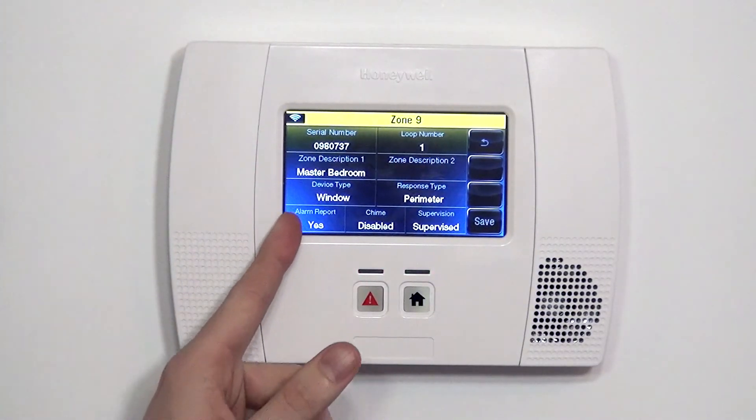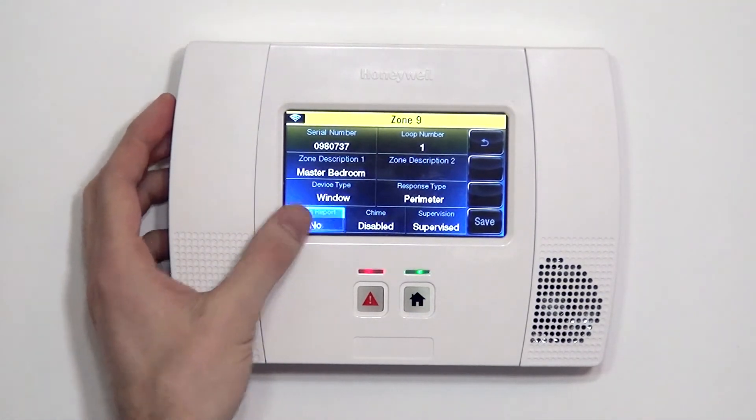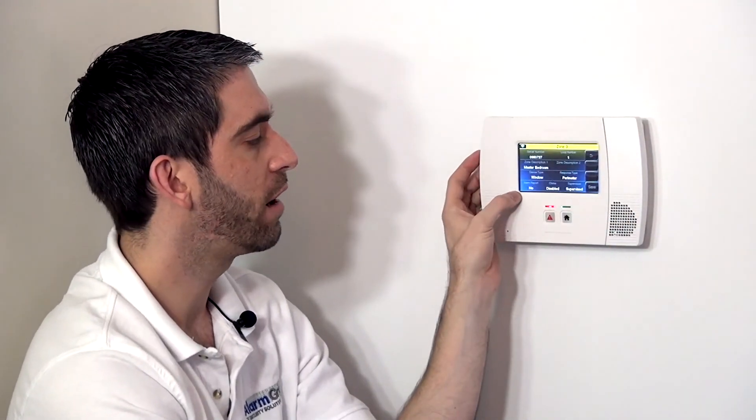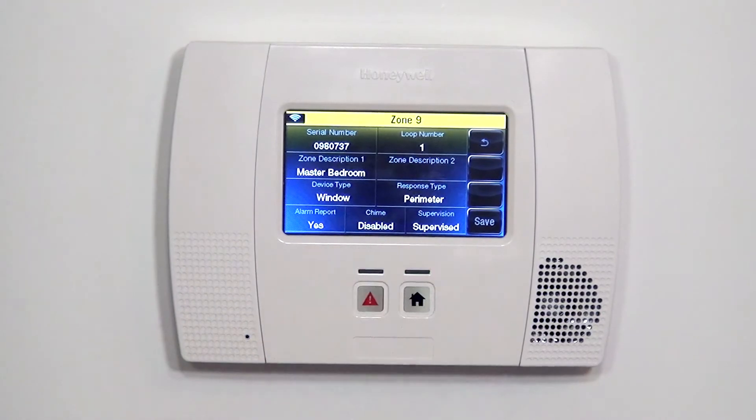Alarm report, this is a toggle, yes or no. Yes means send this alarm to the central station. No means sound the audible alarm in the house, but don't send the signal through to the central. We are monitored and we do want them to respond to this zone, so we're going to set it to yes.